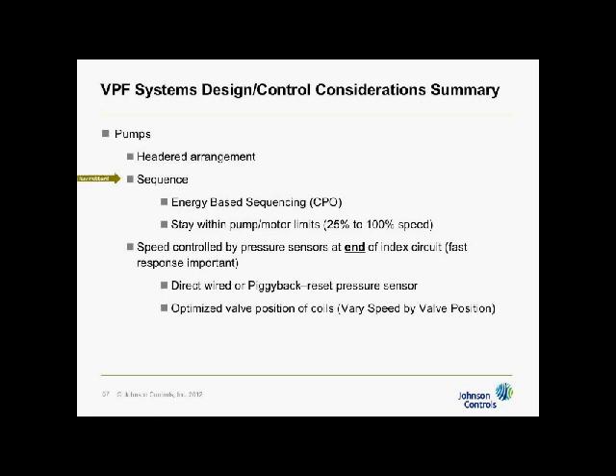Sequence these pumps using energy-based type sequencing because we are talking about doing high-efficiency plants. So you want energy-based sequencing that you'll learn in the next webinar. But we must stay within the pump and the motor limits. Don't go too slow with pumps because you may not be able to lubricate the bearings when you go below 25%. And when you go below 15 hertz, which is 25% of 60 if you're on 60 hertz, and of course it's a little higher percentage-wise if it's 50 hertz, but going below 15 hertz on motors can quite often have the problem of eddy currents and overheating and so on. So we want to make sure that we stay within the pump's limits.